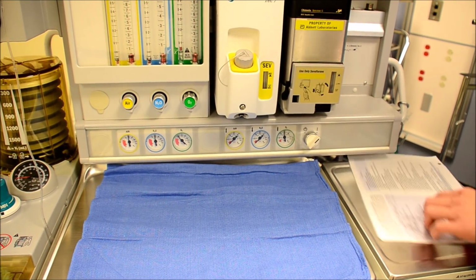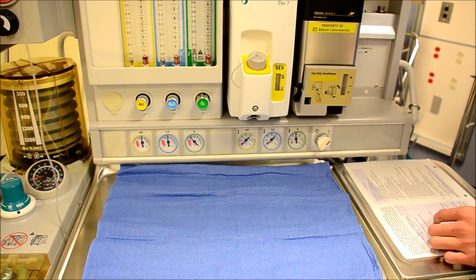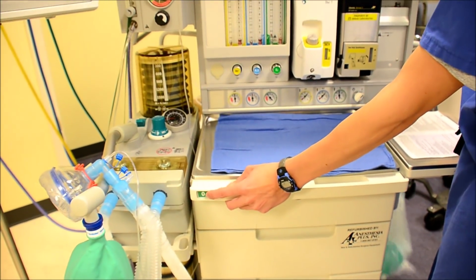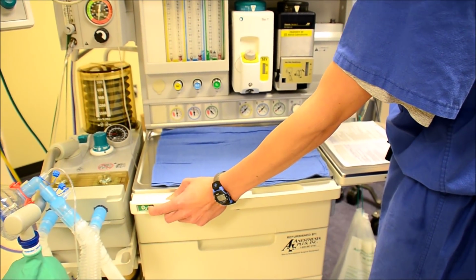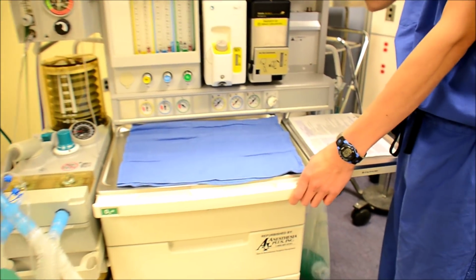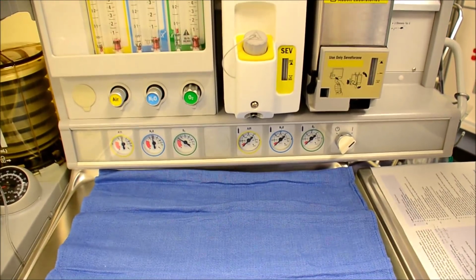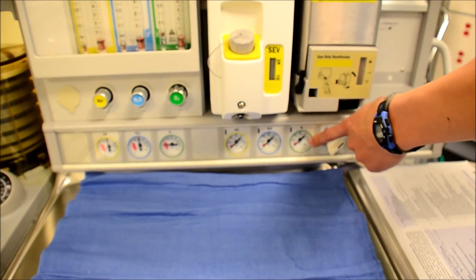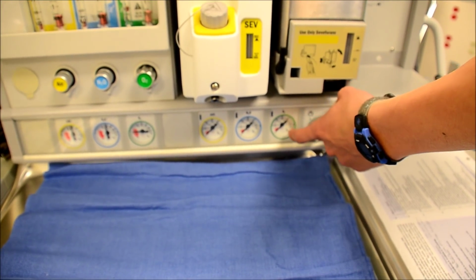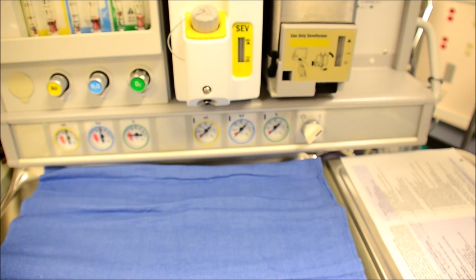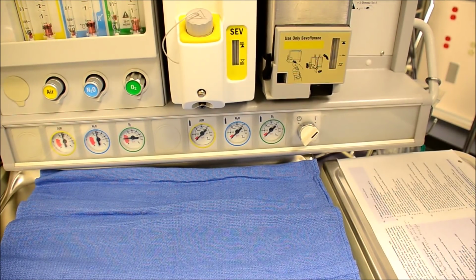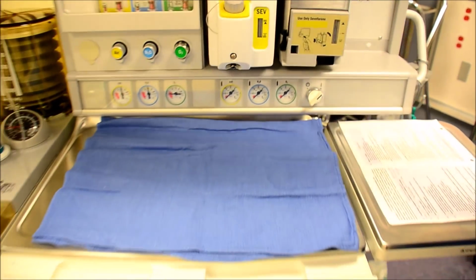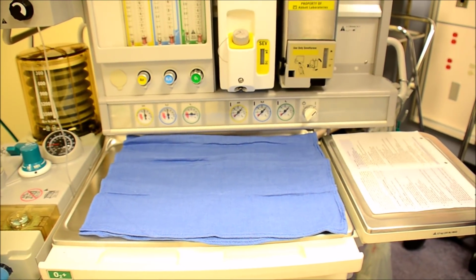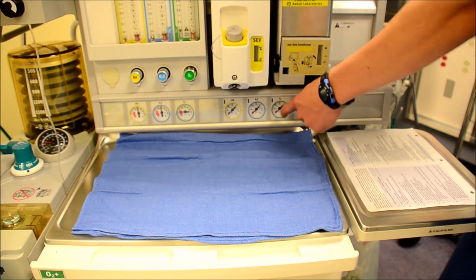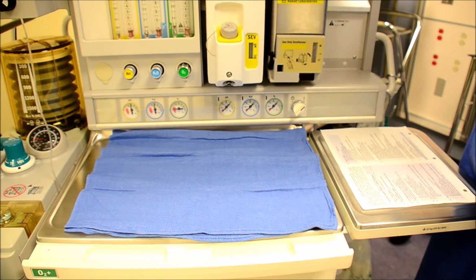Once you close the cylinder off, go ahead and bleed your system with the O2 flush. This O2 flush delivers 75 liters a minute of flow. And so when you bleed your system, you want to make sure your dial reaches 0. That ensures you've successfully closed off your cylinder supply. Otherwise, if there's a connection between your cylinder supply and your mainline supply, you can actually bleed all your reserve supply during the case when you actually need it.